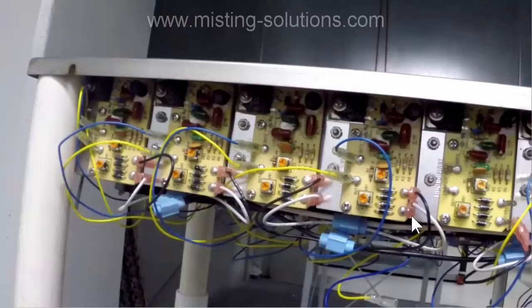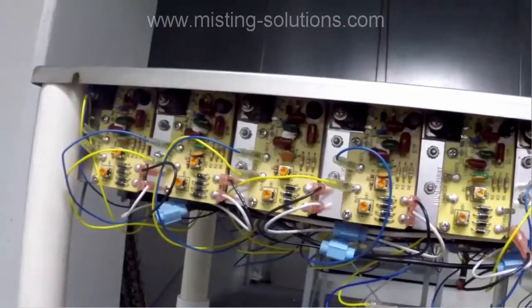And that is the transducer. Now over here we've got a white and a black. So this is the power coming in. This is the 48 volts AC that comes into the board. And here you can see it's a black and a white. And they have to stay in that order. The black is towards the middle and the white is at the edge. And you get the feeling of that quite a bit. I mean, you'll pick up on this because they're all the same. If you question what you're doing, you look at the one that's already in there and you know how to put it together. So here's the board I replaced over here, and you can see that this doesn't have wires on it here and here. So we're putting the wires back on that. I'll start the video.